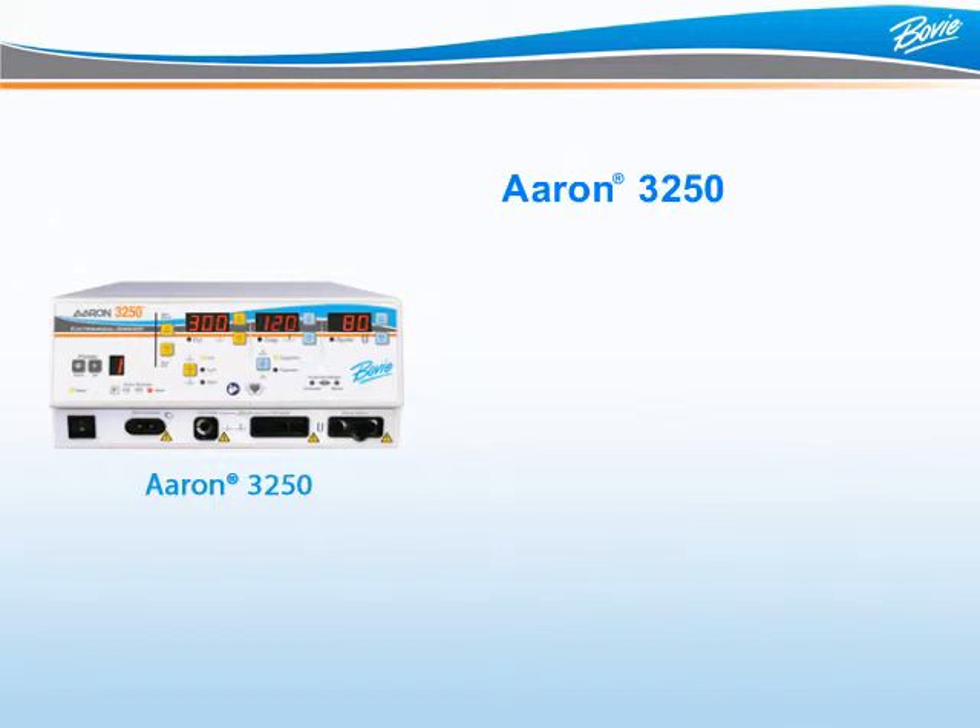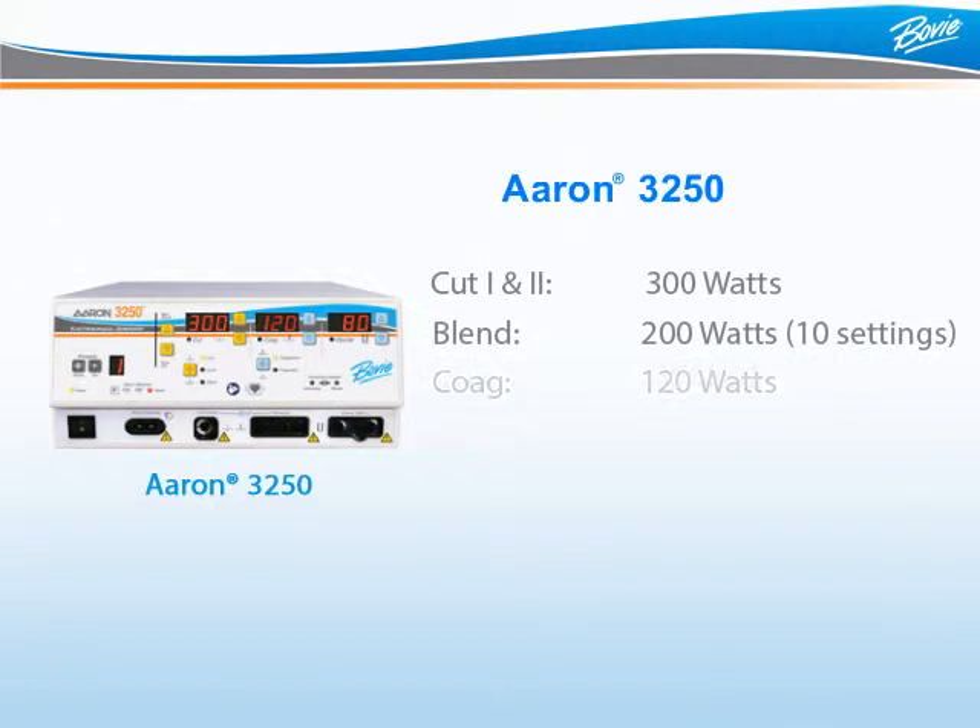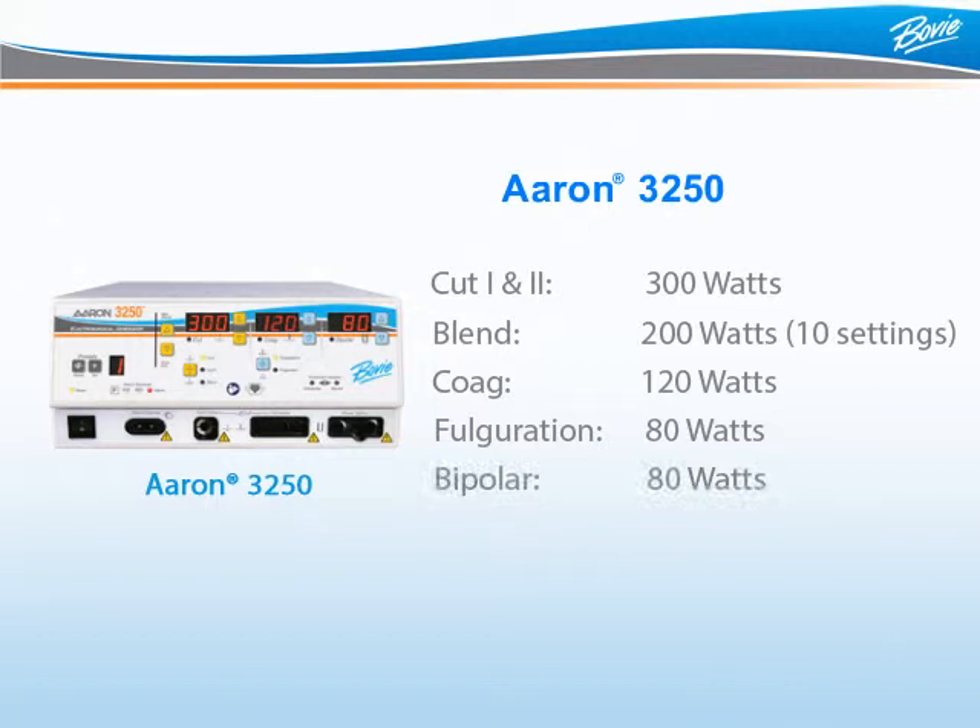This unit features both monopolar and bipolar functions to satisfy all surgical demands. The Aaron 3250 offers 300 watts of Cut 1 or Pure Cut, 300 watts of Cut 2, 200 watts of Blend, 120 watts of Pinpoint Coagulation, 80 watts of Fulguration, and 80 watts of Bipolar.